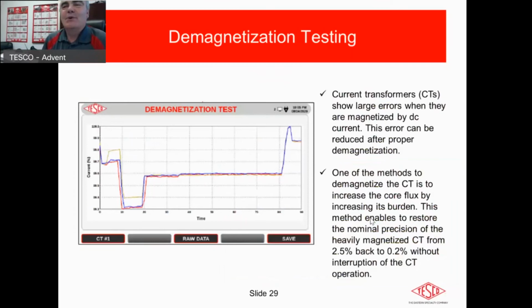So one of the things about your field testing, or even shop testing, because we see this problem in the shop as well, is that you can have magnetized CTs. The problem with magnetized CTs is that they are going to show a fairly large error at times. It's very easy to demagnetize a CT. Basically, you put it into saturation, and then you gradually reduce as you're stepping on down through.